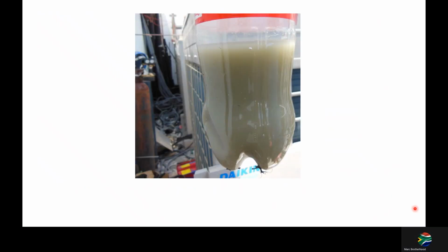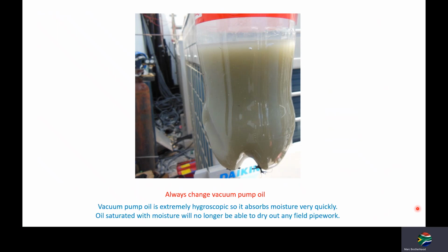Vacuuming. Always change your vacuum pump oil. Vacuum pump oil is extremely hygroscopic, so it absorbs moisture very quickly and readily. Oil saturated with moisture will no longer be able to dry out any field pipework. And just remember that that's what a vacuum does.